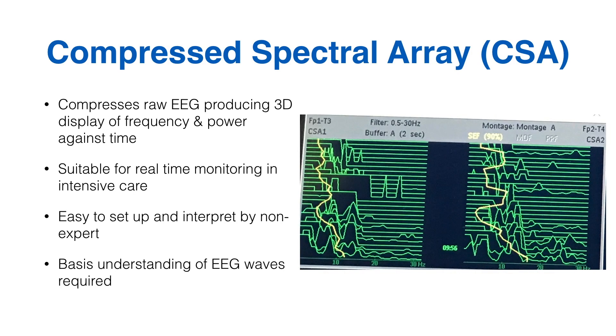For these reasons, there was a need for a system that could be easily set up and interpreted by intensive care staff, allowing continuous real-time monitoring of brainwave activity. One example of this is the Compressed Spectral Array, or CSA. It compresses the raw EEG waves and produces a 3D graphical display of frequency and power against time.